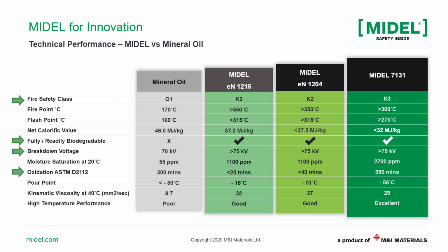The second benefit of esters, why people use them, is because they are biodegradable, readily biodegradable, meaning they have less impact if you have a spillage in the environment from a transformer or during shipment. A mineral oil is not biodegradable at all, and so once you have a spillage, it will be sustained in the environment for a long time, and so expensive cleaning procedures are needed to reduce the impact. On the other hand, MIDEL esters, or esters in general, are readily biodegradable, both the natural esters and the synthetic esters, and so they can allow reduced bunding and reduced procedures for cleanup in case you have spillage with minimized risk on the environment.